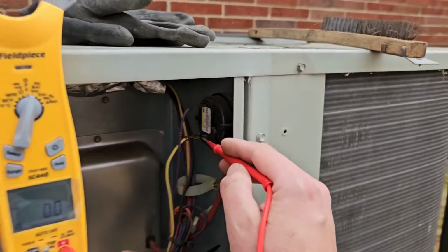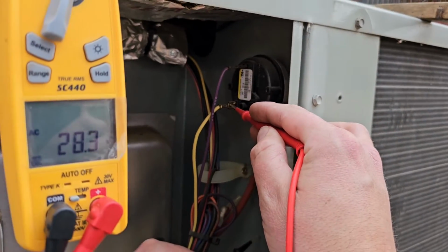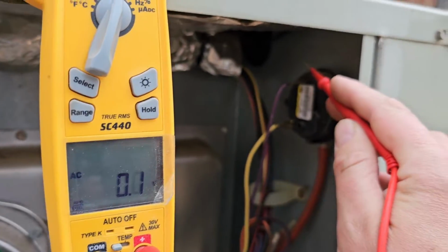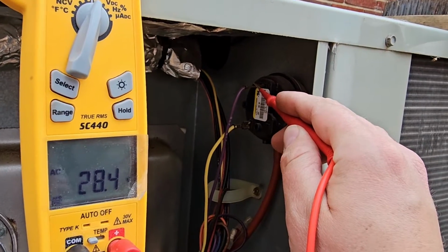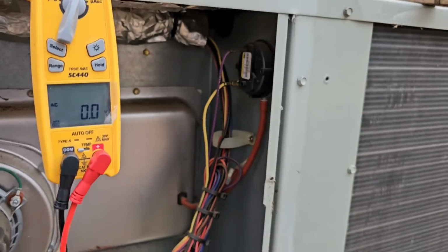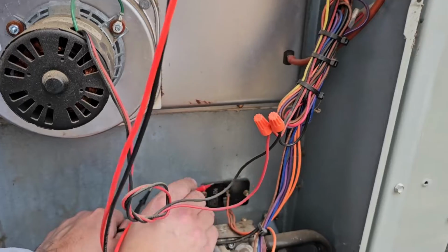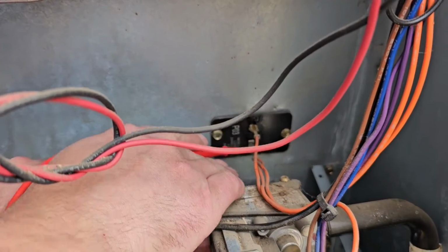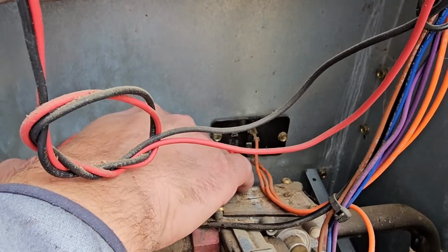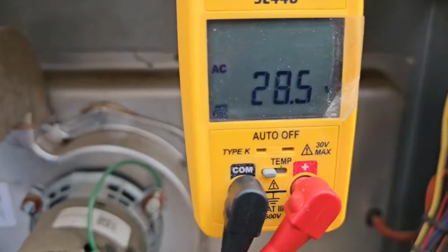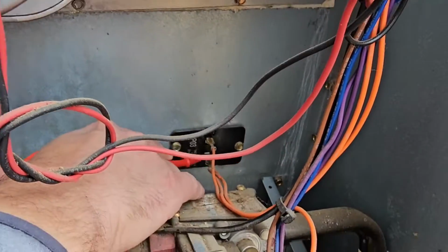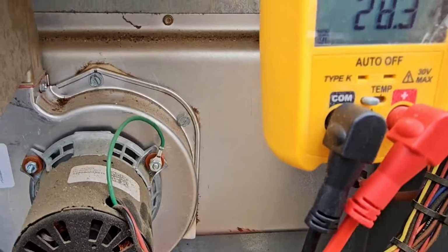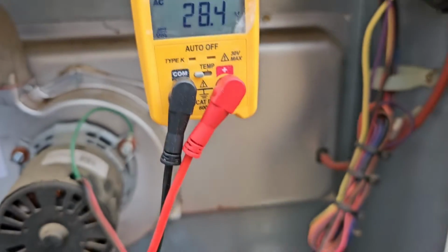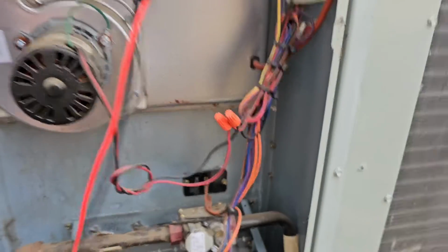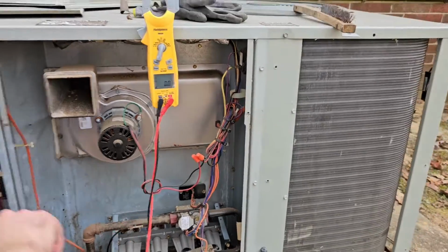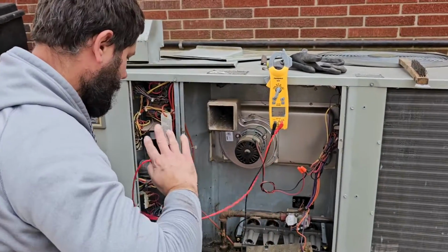Now let's go with the pressure switch. All right, this side 28, and then this side 28. That's closed. Now we're going to go to the limit switch down here. Take a look at the limit switch. Go to the bottom wire first. What do we got? 28 volts. Go to the top wire. All right, 28 volts. You just heard a click, and that's for the indoor motor. All right. So our indoor motor should be running.